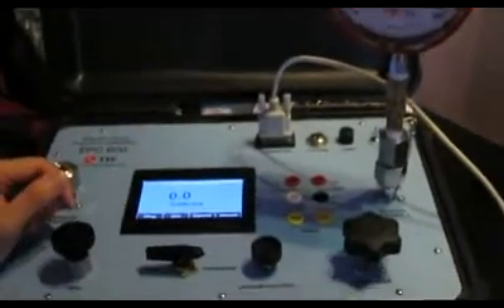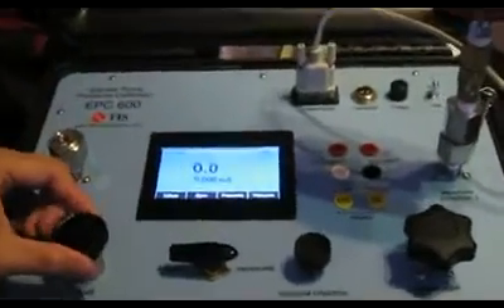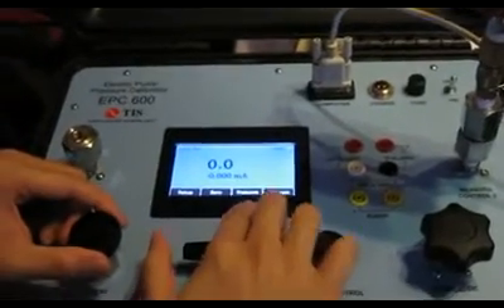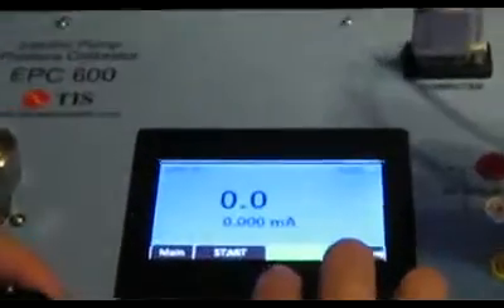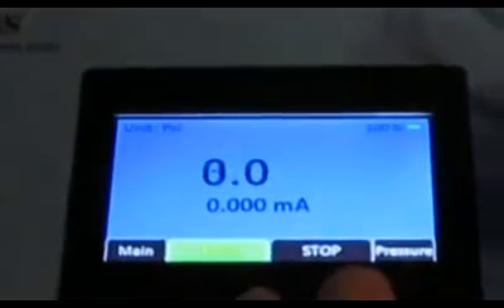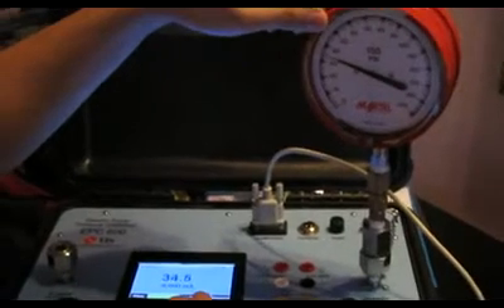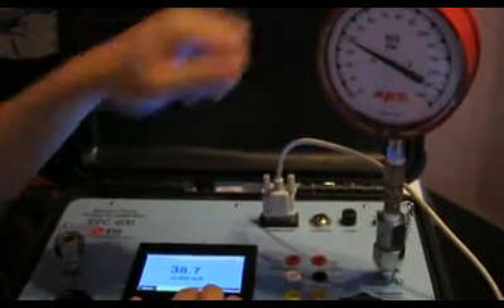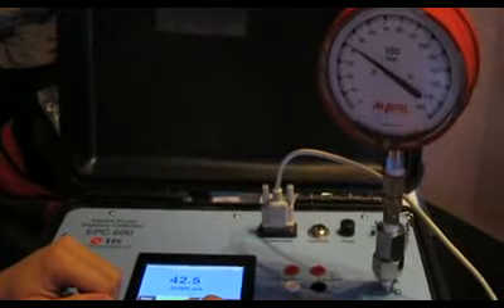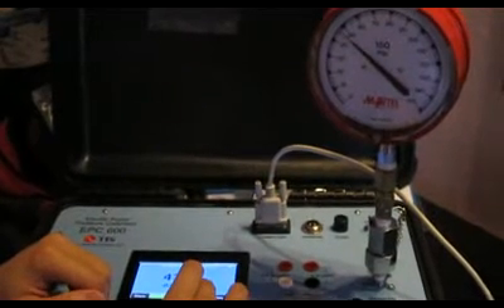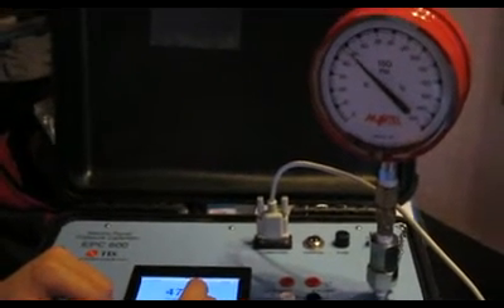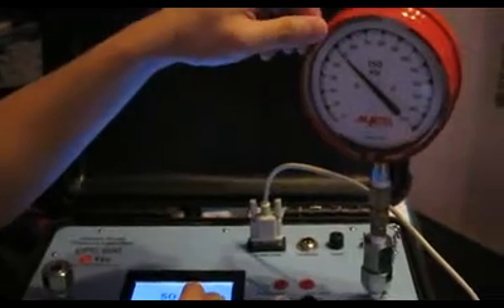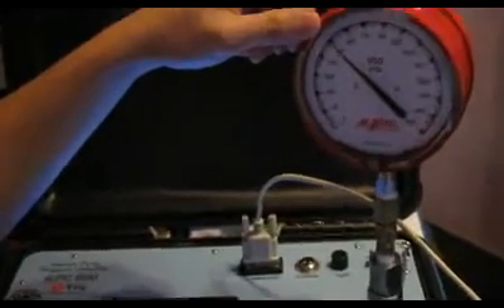Next, we need to generate pressure up to 50 psi. Simply press on pressure and start. Now we simply need to focus on the test gauge. At 50 we will stop the pump. At 50 psi, once the pump is stopped, we hit enter.